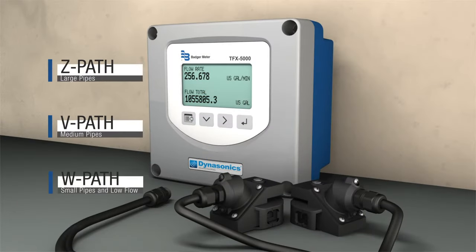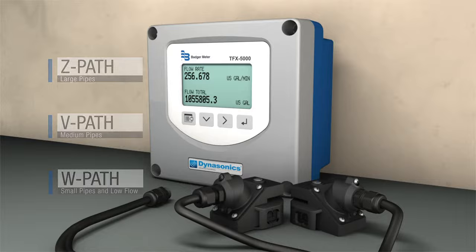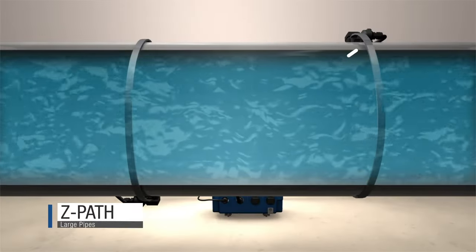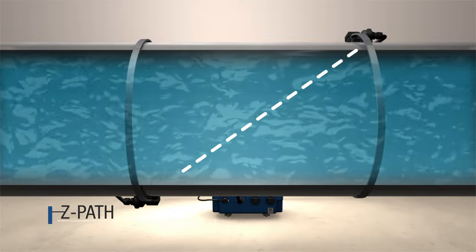Clamp on transducers can be positioned in multiple ways. A Z path or 1 traverse is typically used on large pipes. The signal is strongest when it travels this type of path.